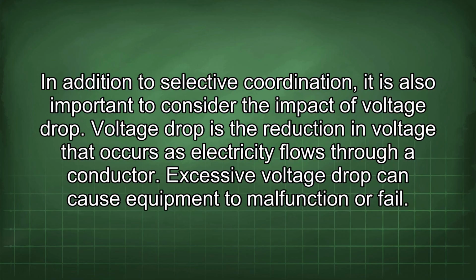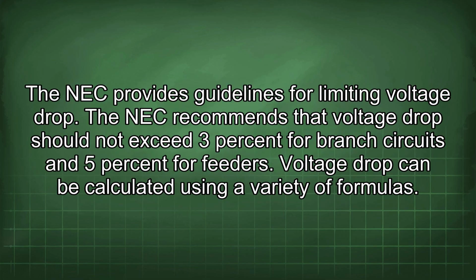In addition to selective coordination, it is also important to consider the impact of voltage drop. Voltage drop is the reduction in voltage that occurs as electricity flows through a conductor. Excessive voltage drop can cause equipment to malfunction or fail. The NEC provides guidelines for limiting voltage drop. The NEC recommends that voltage drop should not exceed 3% for branch circuits and 5% for feeders.